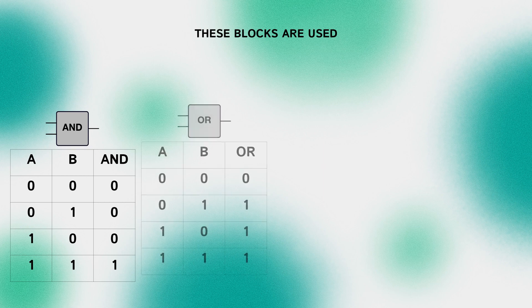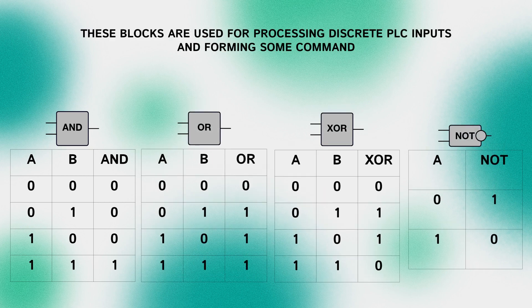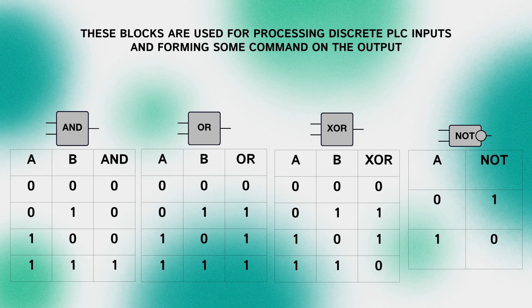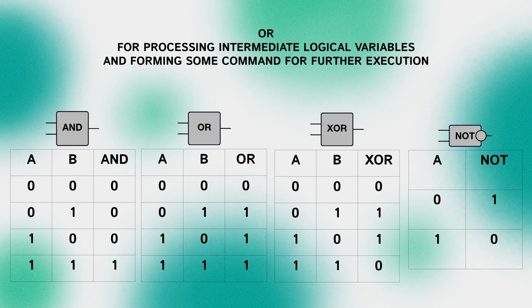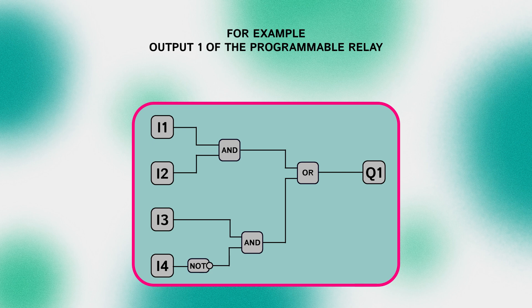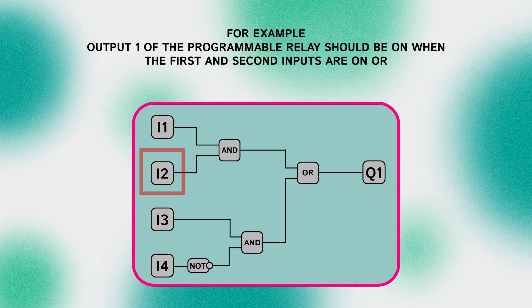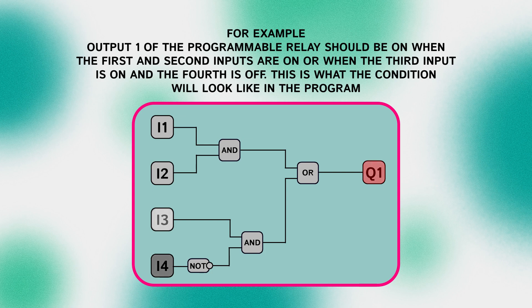These blocks are used for processing discrete PLC inputs and forming some command on the output, or for processing intermediate logical variables and forming some command for further execution. For example, output 1 of the programmable relay should be ON when the first and second inputs are ON, or when the third input is ON and the fourth is OFF. This is what the condition will look like in the program.